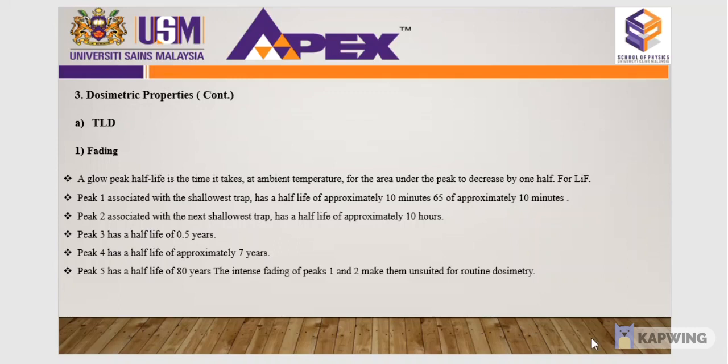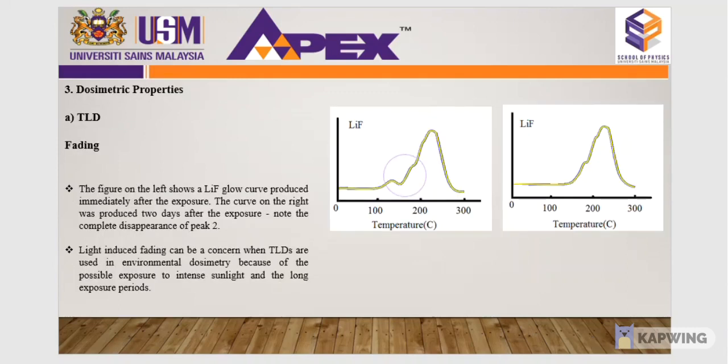Okay, the figure on the left shows LiF, representing a glow curve produced immediately after the exposure. The curve on the right was produced 2 days after the exposure, note the complete disappearance of peak 2.